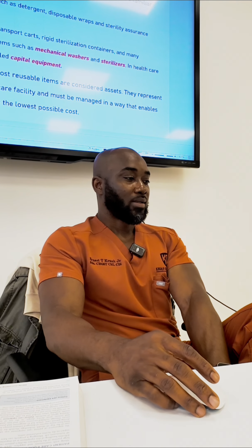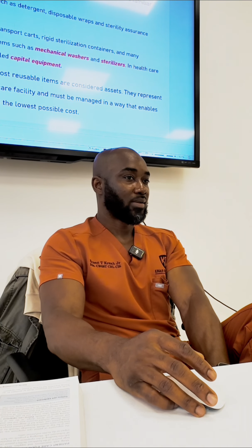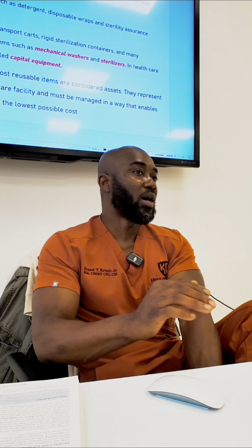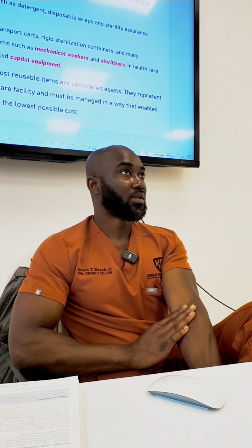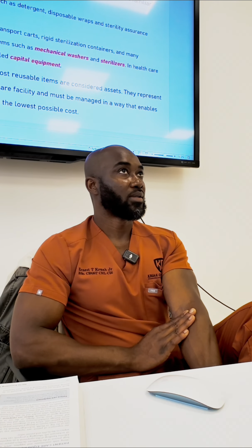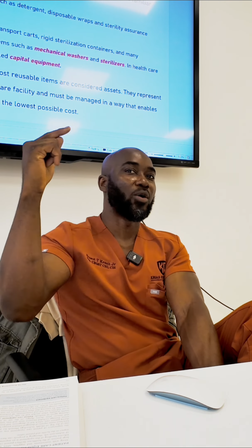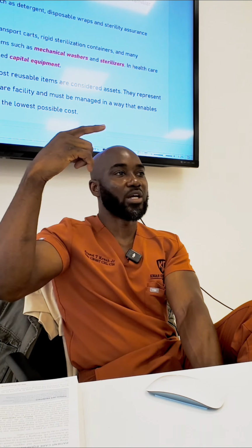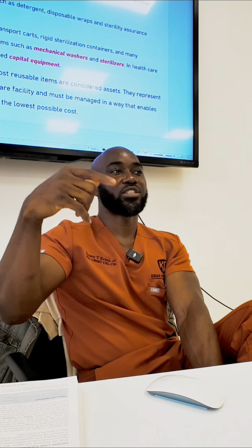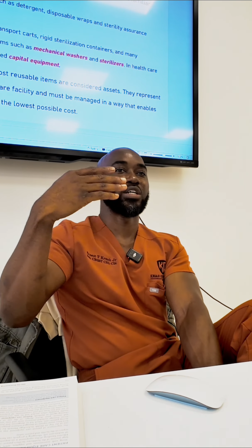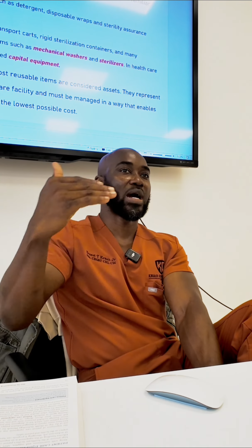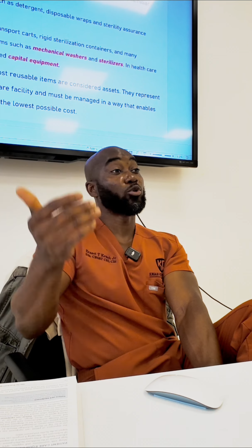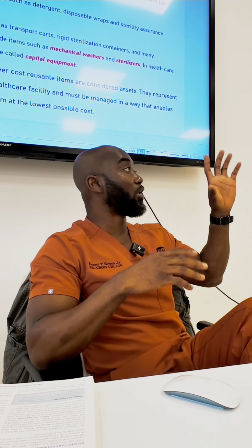Okay, I see. So this is not on the actual autoclave, it's next to it, correct? What's next to it? The screen is next to the autoclave. Yeah, the screen. Some autoclaves have a digital screen that tells you what's going on. It tells you the ongoing process, which phase of sterilization it is in: the conditioning phase, the drying phase, the exposure phase. So you can tell all of these things just by looking at the screen.